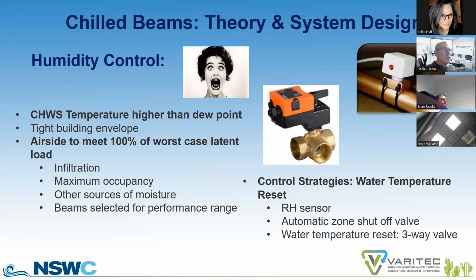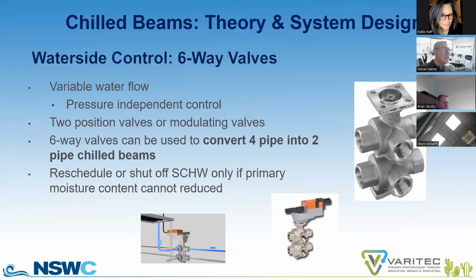So there are strategies for humidity control in a space in the event that space dew point exceeds chill water temperature. We can actually register that through an RH sensor in the space or strategically located at various points in a floor, and then do an auto temperature reset to a zone using a 3-way valve where we bleed return water from the chill beam loop back into the supply water conditions so we maintain an adequate supply water temperature to the beam to prevent condensing.